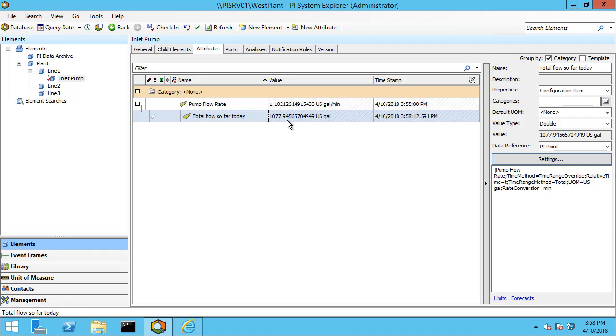As a reminder, this is the total flow from T at midnight today on this client machine to star, since PSE is passing an end time context of now. This could look slightly different if you're on a different machine, since T could resolve to a slightly different time because it'll be midnight local to that time zone. Also, the end time context may be slightly different if, for instance, your PI Vision display doesn't have an end time of now.